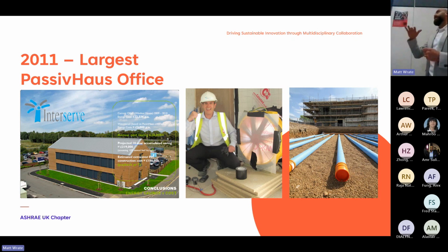The process of learning when the blinds go up and when the heating comes on was a really interesting learning experience, and it took many attempts to get right. We want the sun heating the building, so when it drops below temperature we want the blinds to open, but how long do you allow before the heating kicks in, because people complain about the cold? There were lots of little teething issues that took a long time for us, and the users, to work out. In summer you'd feel warm as the sun came in before the blinds reacted, and the first thing people would do is open the window - but that just brings in the hot 32-degree air rather than the 22-degree air from the earth tube system.